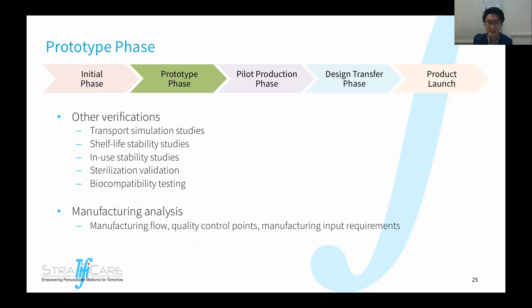One big chunk of activities during this phase is design verification, where you have to go through all the different tests to make sure that your product actually meets your predefined engineering specifications. All these tests again need to be statistically analyzed, and the sample size of the tests has to be predetermined. Some other things we usually don't consider in the academic setting are transport simulation studies, shelf life, in-use studies, and for implantable medical devices, sterilization and biocompatibility. And last but not least, you have to think about how you're going to manufacture it: looking into the manufacturing flow, quality control points, and the manufacturing input requirements. For the rest of the three phases, it's really next to impossible to run them in an academic setting, so I will leave it for now.